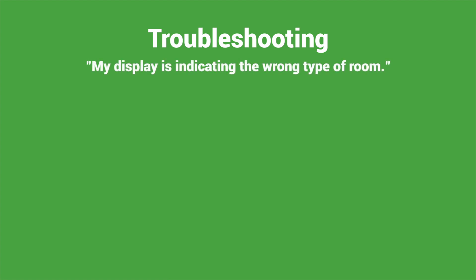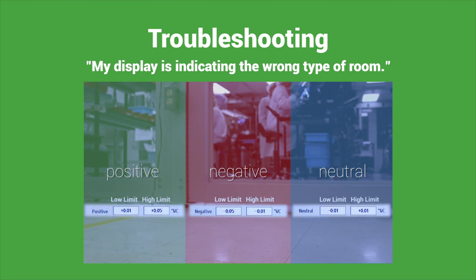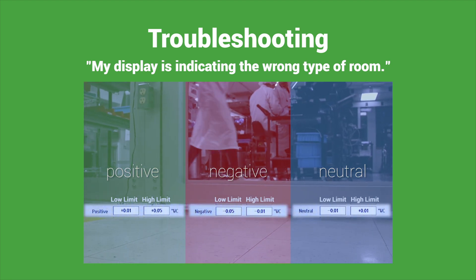If you have a negative room but the display is indicating positive room, check the alarm set points. Make sure they correspond to the proper kind of room.